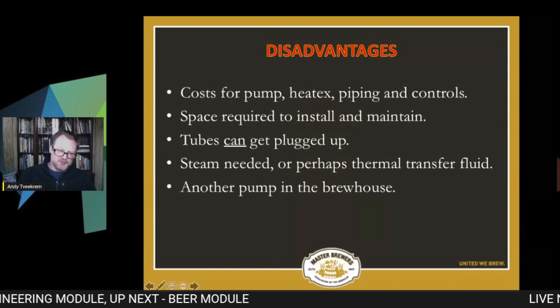If you're dumping a bunch of sugar into your kettle, making a strong beer, you want to leave the thing running with the wort going through it, but turn the steam off for about 5 minutes or even 10 minutes. Make sure everything's dissolved before you turn the steam back on. Otherwise, you can bake those sugars right into the tubes, and then everything's going to get fouled up, and that's a problem. But unlike an internal cooker, which typically is just a tube bundle sitting in the body of the wort, it relies on convection to move the wort through. Those tubes, if they start to get fouled up, the fouling just gets worse and worse because the flow is more limited. And the more limited the flow is, the more excessive the baking on of the solids is, because there's nothing forcing it through.